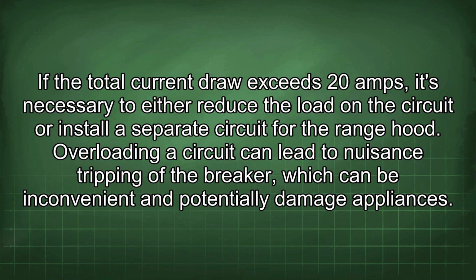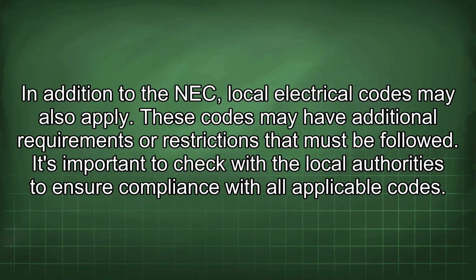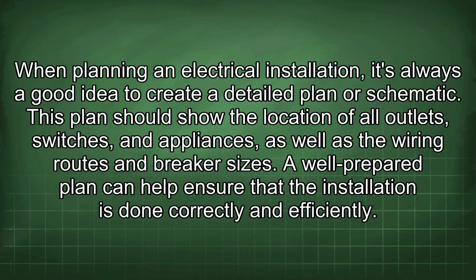If the total current draw exceeds 20 amps, it's necessary to either reduce the load on the circuit or install a separate circuit for the range hood. Overloading a circuit can lead to nuisance tripping of the breaker, which can be inconvenient and potentially damage appliances. In addition to the NEC, local electrical codes may also apply. These codes may have additional requirements or restrictions that must be followed. It's important to check with the local authorities to ensure compliance with all applicable codes. When planning an electrical installation, it's always a good idea to create a detailed plan or schematic.